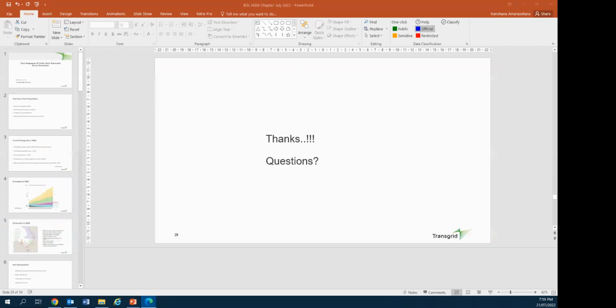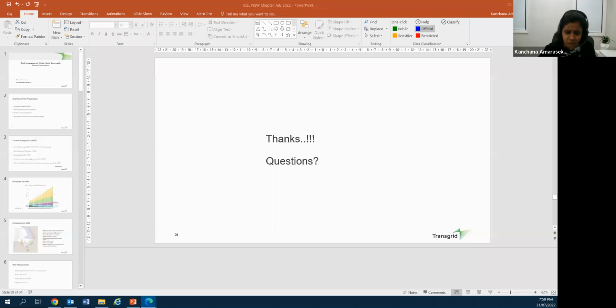Hi. Hi, Ashini, we can hear you. Yeah, just regarding the grid following systems. So do they have the black start program capability? No. No, they don't basically, Ashini. They will struggle to operate without that grid voltage waveform. So they rely on the grid voltage waveform as if they cannot track the angle, or if there's no grid voltage waveform, they struggle to operate.